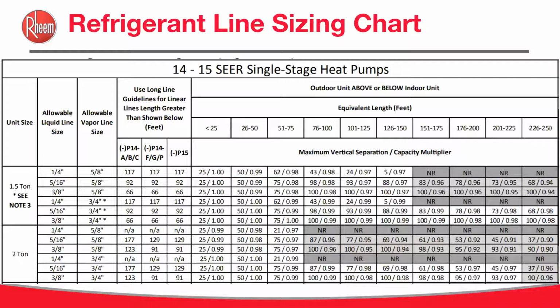But then we have the fittings. Each fitting used in the line connections have equivalent fitting lengths. These are associated with them and are added to your actual linear lengths. This will help to determine actual diameter of the refrigerant tubing required. So the actual length of the piping is used for rough charging purposes only.